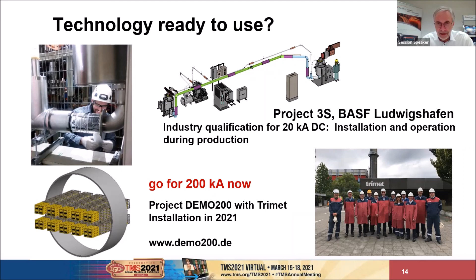This year, we will do an installation at TRIMET aluminum plant in Essen, which is also in Germany. And we are going to install a busbar system as a demonstrator for 200 kiloamp. So it's just a factor of 10 above the 20 kiloamp. And this is called Demo 200. And below there, you see the website. You can visit the website of Demo 200. It will be installed in a cryostat with an outside diameter of, let's say, 350 and maximum 400 millimeters. 200 kiloamp enclosed in 400 millimeters maximum is a tremendous advantage.